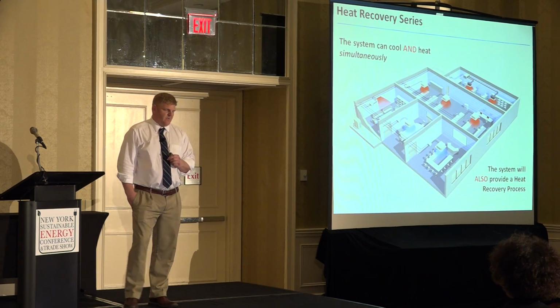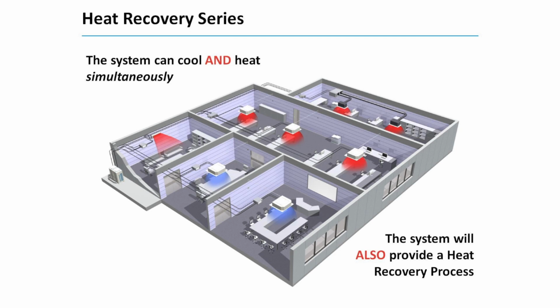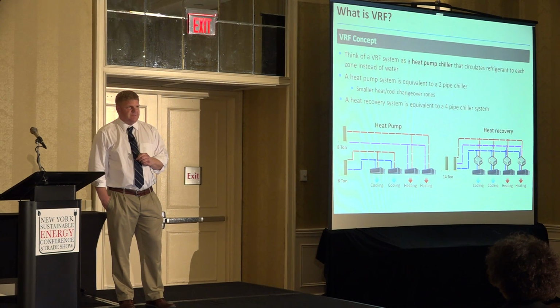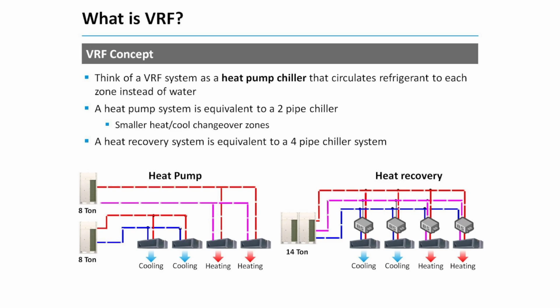But a heat pump system will essentially either be in heating or cooling, not simultaneously. And then we also have what we call our heat recovery system, which you could be in an office and there could be a conference room in cooling while another office would be in heating. So you could have simultaneous operation. Essentially, we can think of it that a heat pump is a two-pipe chiller. So these are essentially chillers that circulate refrigerant instead of water. So a heat pump would be a two-pipe chiller, and I'm going to call the heat recovery system a four-pipe chiller.